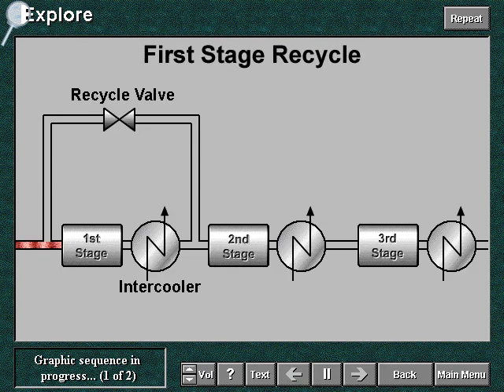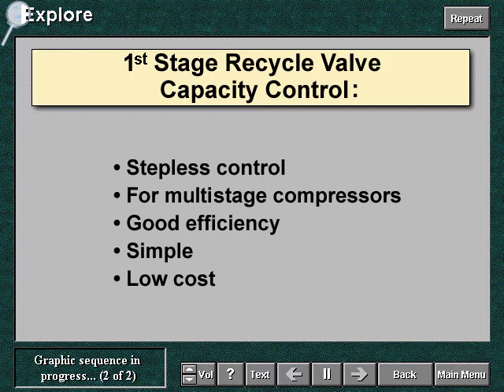Recycle controls capacity by recirculating a portion of the gas from the first stage delivery back to its suction. This system is suitable for multi-stage compressors and works by reducing with the recycle the quantity of gas that is sent to the second stage and beyond. The gas amount recycled around the first stage can be varied continuously. The system therefore is a continuous type control. The first stage handles 100 percent of the gas under capacity control, but the following stages handle only the reduced flow rate. Therefore, the efficiency of the system is good and increases with the number of stages. First stage recycle is simple and of low cost.